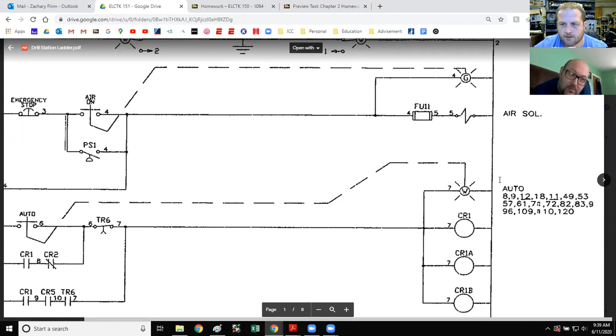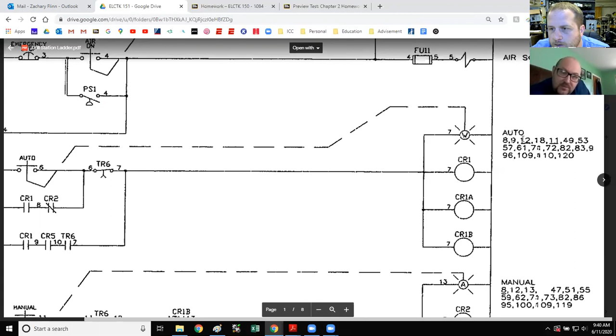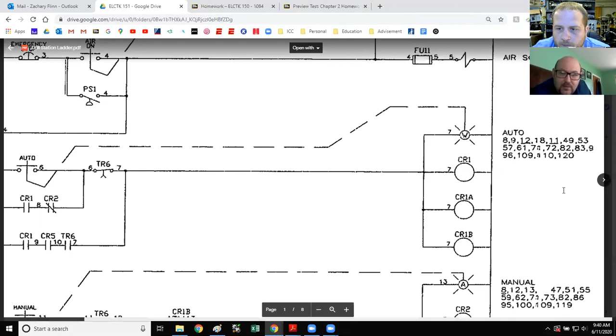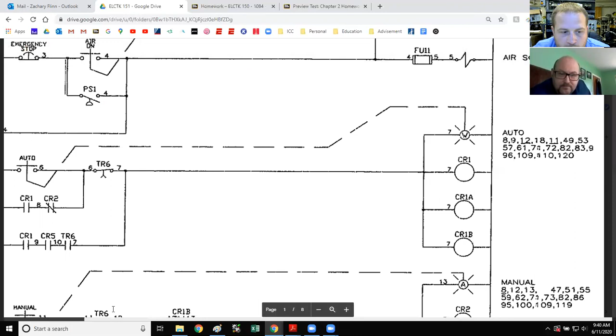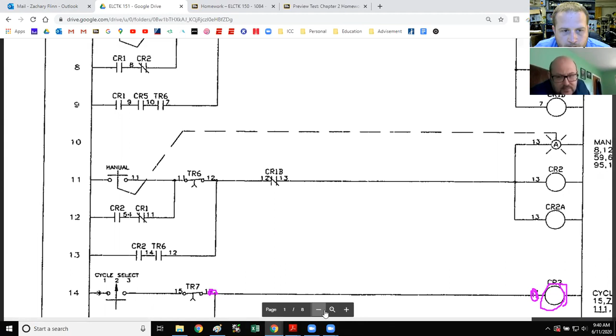All right, so all this mumbo jumbo right here means that there are contacts elsewhere in the ladder diagram that these coils are associated with. So if I want to know where else, let's see, if I look at rung 12, it's underlined. So if I go to rung 12, I bet you I'll find CR1, CR1A, or CR1B normally closed contact there somewhere. Let's go to 12. CR1, normally closed, see that? Yes, does that make sense?